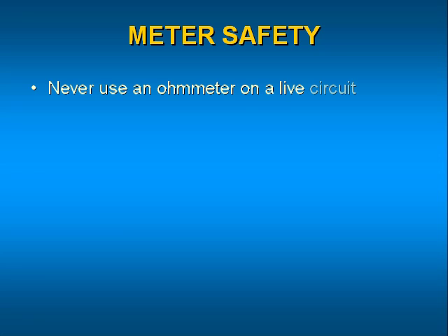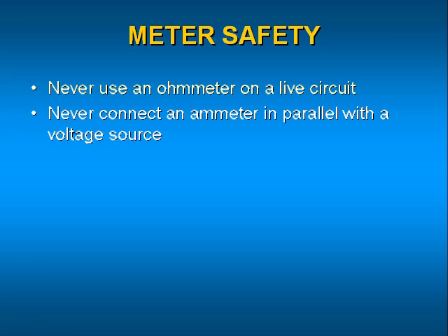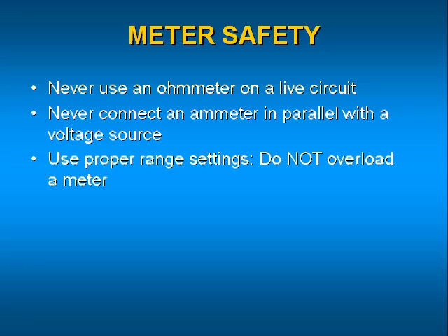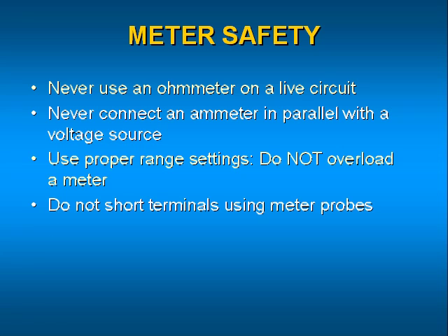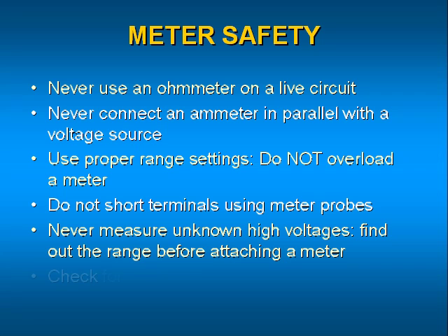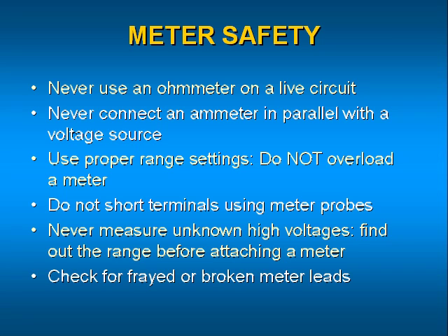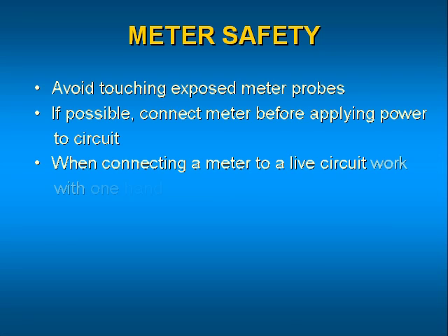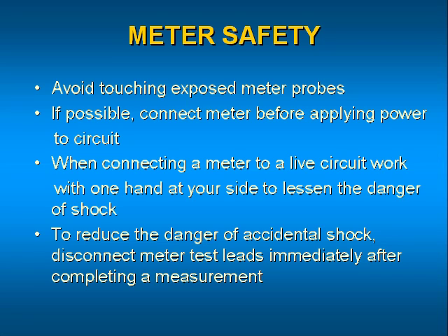Proper use of a meter protects the meter and its operator from damage and injury. Here are a few very important guidelines for the use of meters. Never use an ohmmeter on a live circuit. Never connect an ammeter in parallel with a voltage source. Use proper range settings. Do not overload a meter. Do not short terminals using meter probes. Never measure unknown high voltages. Find out the range before attaching a meter. Check for frayed or broken meter leads. Avoid touching exposed meter probes. If possible, connect the meter to the measurement points before applying power to the circuit. When connecting a meter to a live circuit, work with one hand at your side to lessen the danger of a shock. To reduce the danger of accidental shock, disconnect meter leads immediately after completing a measurement. No matter how careful you are, you will make some mistakes using a meter. Just make a mental note to try and make as few mistakes as possible.